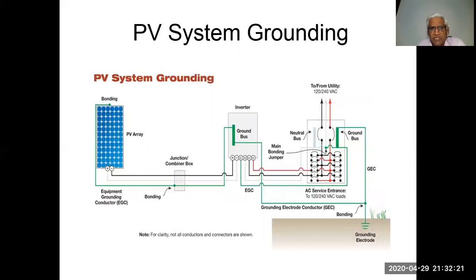PV system grounding. You notice that on the left side we have a PV panel, or a module, or an array, and this is the grounding bus here. The inverter is also seen here, and this is a grounding bus. So from one side a connection goes from the grounding bus to the array, and on the other side the same kind of connection goes to the ground and to the ground bus. The connecting wire is called the EGC.